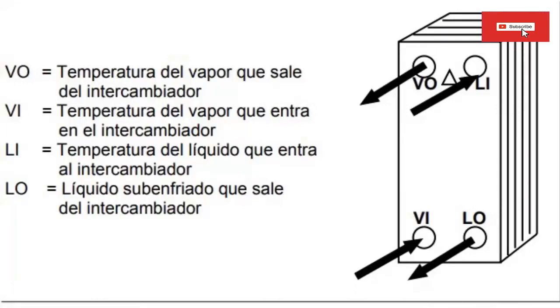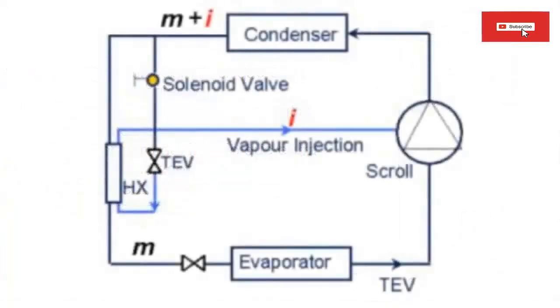27. The liquid refrigerant piping between the economizer and the evaporator should be insulated and kept as short as possible to minimize heat gain. 28. The vapor injection pipe connecting the exchanger to the compressor must be three-eighths to a half inch in diameter.